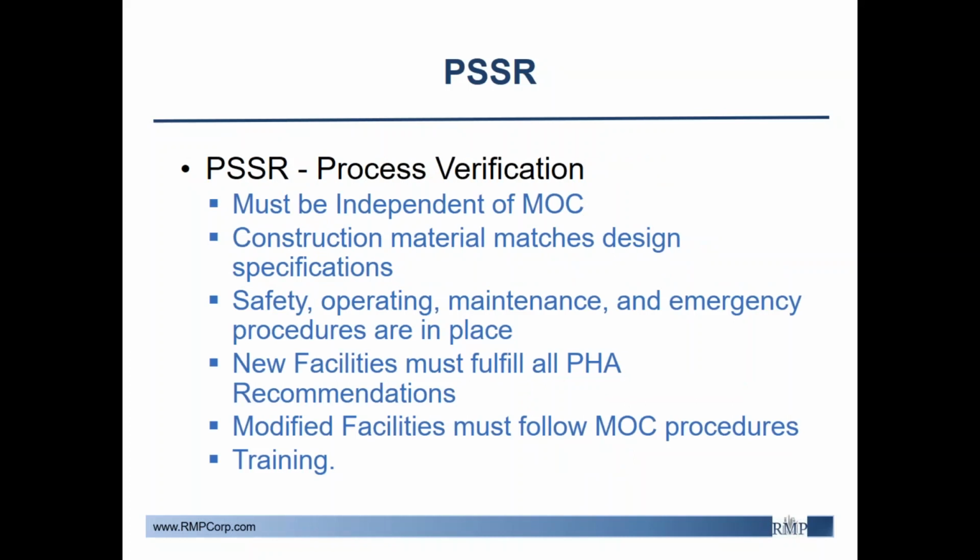So what we touched on is they're often combined with the MOC process, but it needs to be independent, essentially. And what that means is that you don't just rely on the MOC form to say, you look through it and go, okay, they've done the operator procedures check, they've done the safety review, they've done the construction according to the MOC form, right? It should be a team that looks through on their own without looking at the MOC form to make sure that all the construction materials match the design specification.